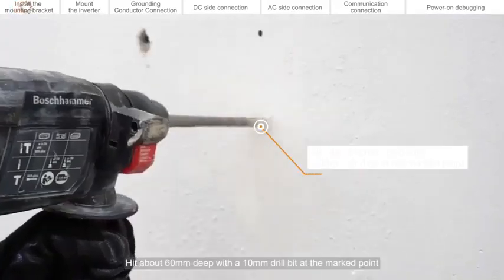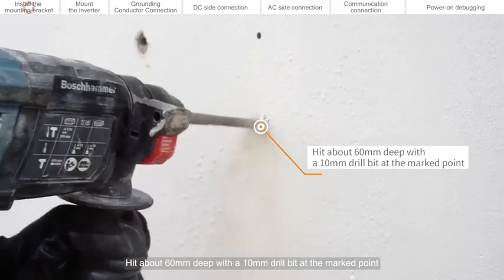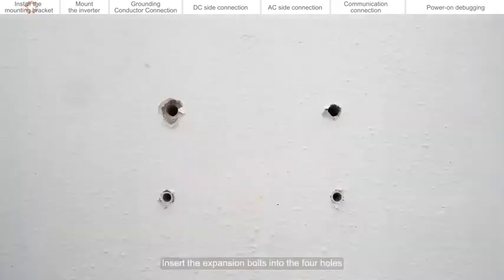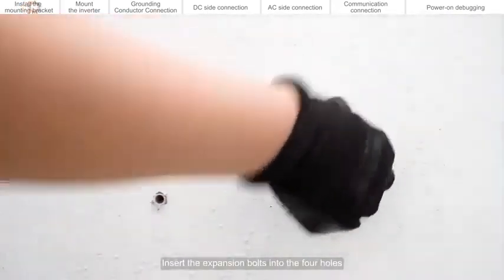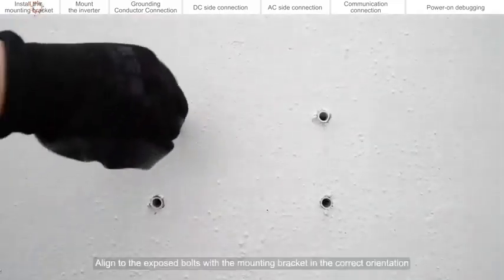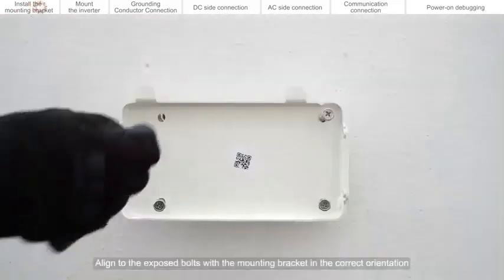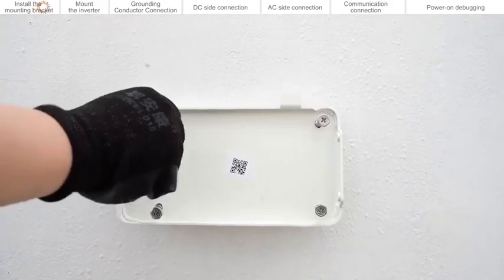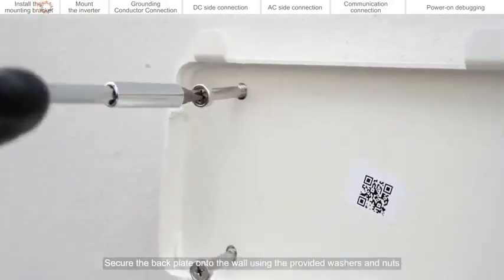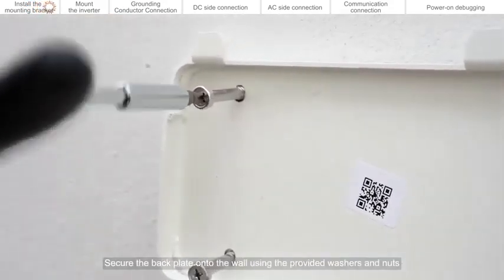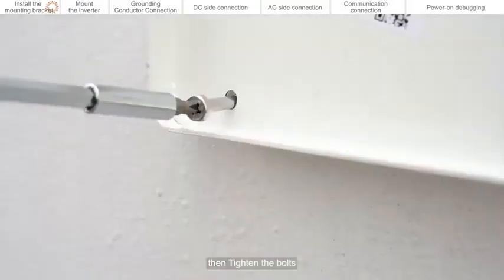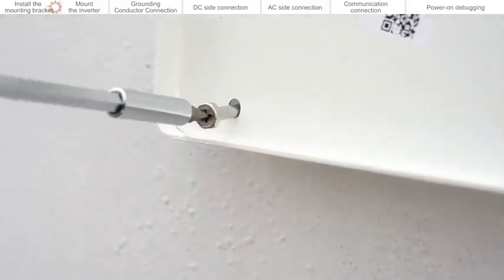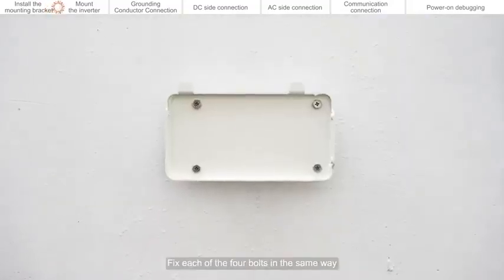Drill about 60 mm deep with a 10 mm drill bit at the marked point. Insert the expansion bolts into the 4 holes. Align the exposed bolts with the mounting bracket in the correct orientation. Secure the back plate onto the wall using the provided washers and nuts. Then tighten the bolts. Fix each of the 4 bolts in the same way.